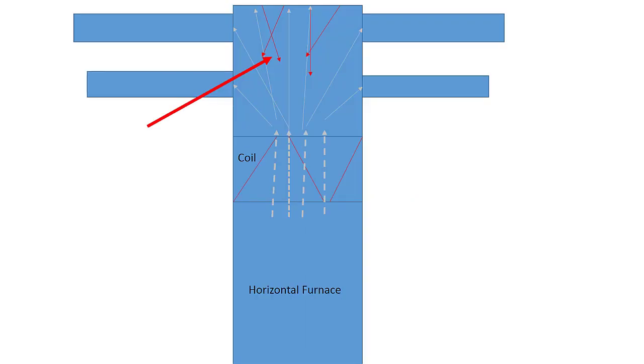Here's another standard example of a fan coil or in this case a horizontal furnace with a box on the end of the furnace with a coil. You notice that the fittings going out into the ductwork are just straight pipes off of the box. Each one of these fittings is 35 feet equivalent length.